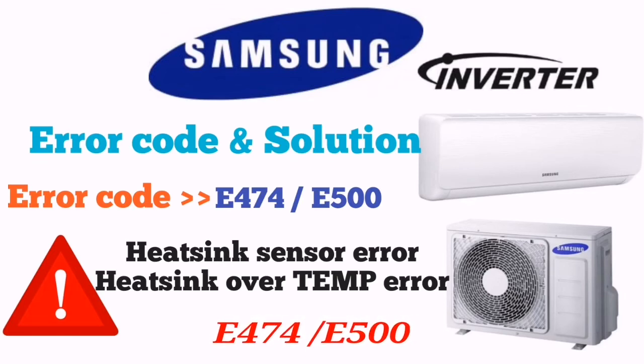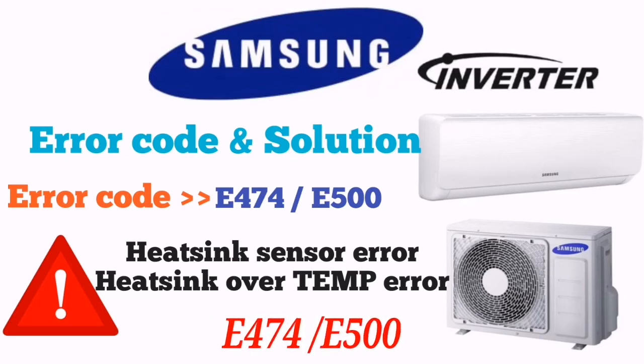If your fan operation is not normal, then you have to check the connection of your fan motor, or you have to change the fan. Or even if all these are okay, if it is showing the error again, then you have to change the outdoor PCB and it will be in working condition.